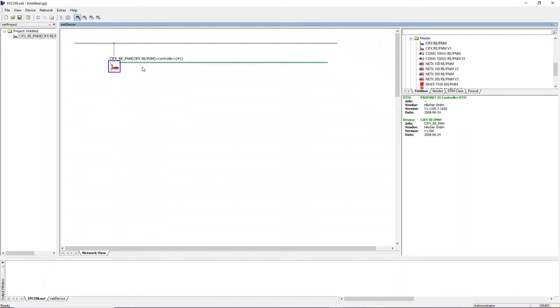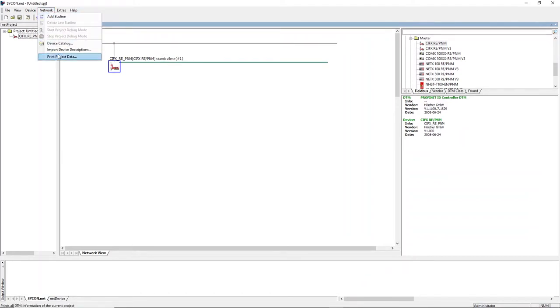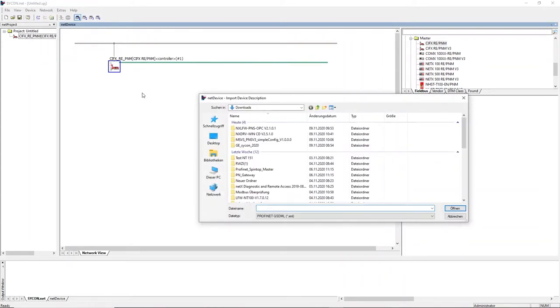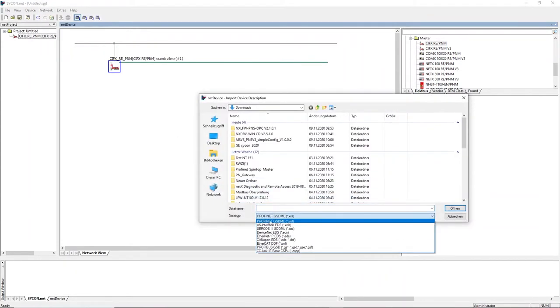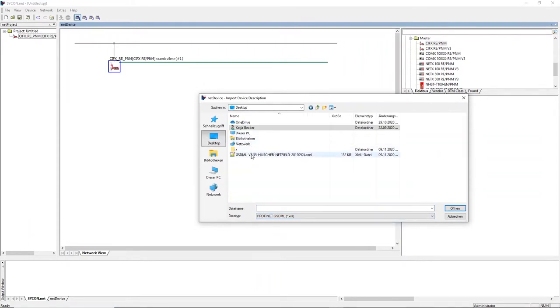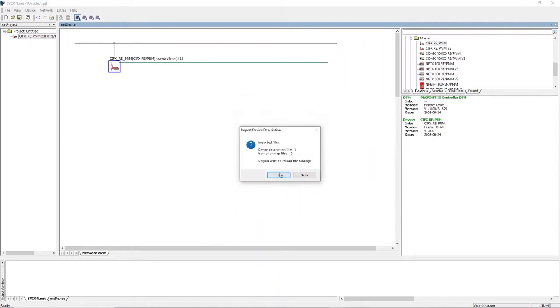To add the NetField IO device to the PROFINET network, which is shown as a green line in Sycon.net, first add it to the device catalog by importing the device description. Select network import device description, check for the correct data type, and select the NetField GSDML file. Accept the upcoming window to reload the device catalog.